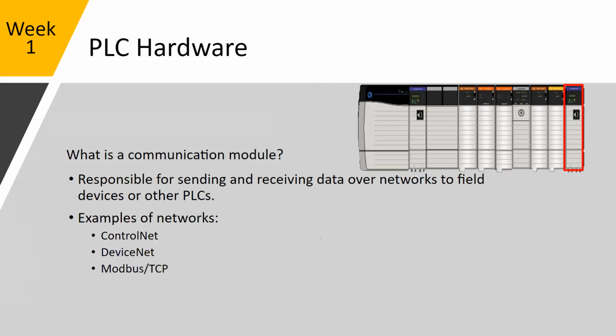So communication modules. These are responsible for sending and receiving data over networks to field devices. So you can have any number of different types of devices. And 10 years ago, when somebody would talk about an Ethernet module for PLCs, you almost exclusively were talking about how you communicated with the PLC. But now there's a lot of different devices out there which will talk on some of these control protocols. So for example, Allen Bradley has ControlNet and DeviceNet. Those are proprietary kind of comm modules, like communication protocols that Allen Bradley has developed.